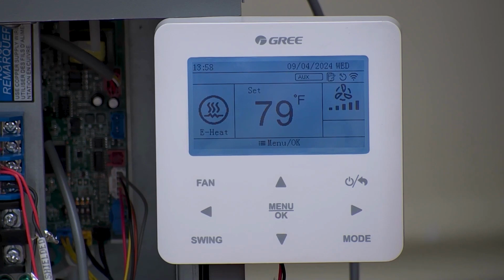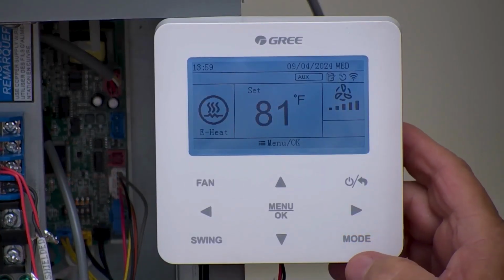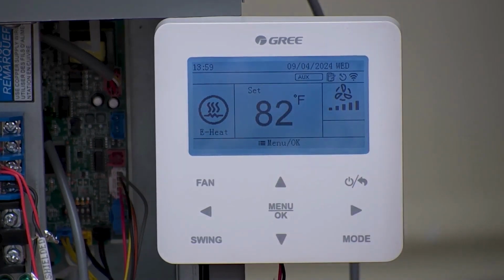So the other thing that we gained while we're waiting on that for a minute, the other thing we gained with this, and I've tested this myself, even if I lose power to my outdoor unit, which normally would give you a communication error code, and you lose all function of the GREE MultiPRO unit. You will lose all function to the GREE MultiPRO unit. But as long as that blower motor can still work and the board is still good, you will still have E-heat function. Again, it might be because I cycled it so quick. It's probably got a delay in it. But we'll give it a minute, see if it don't kick back in here.